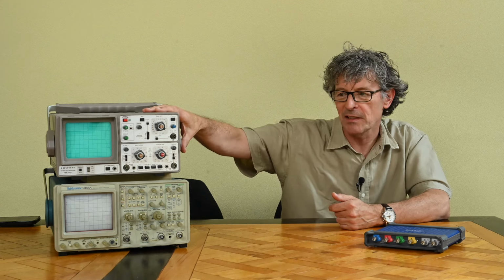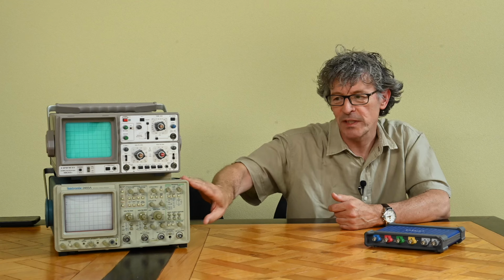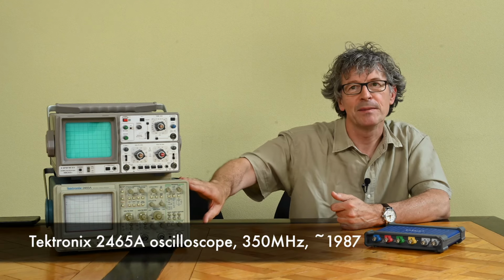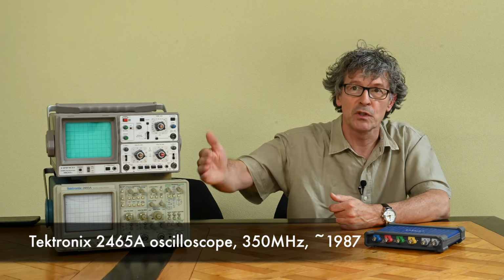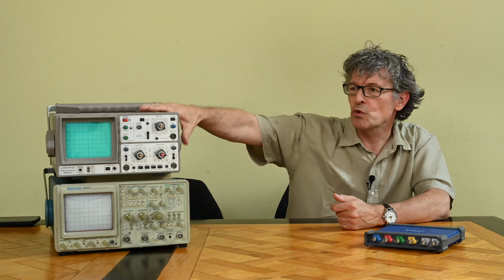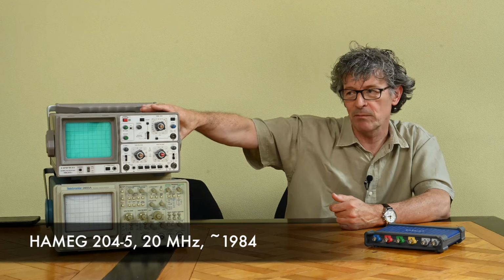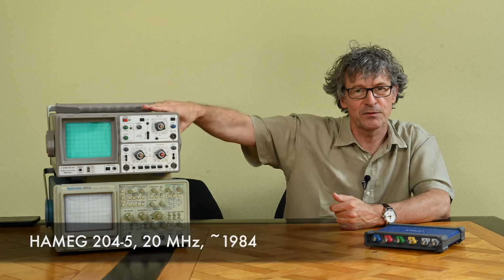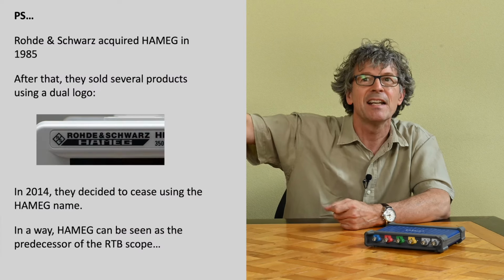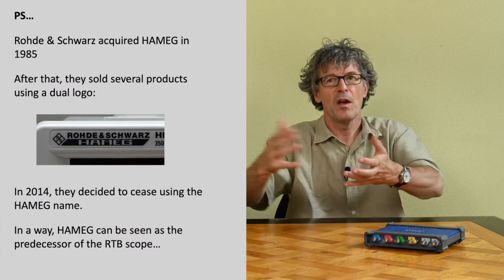Math functions have been with us on oscilloscopes for a fairly long time. I've got two oscilloscopes standing right here, a Tektronix 350 megahertz, I think. It has addition, it has invert, so you can also do subtraction. Also my Hameg scope, I think I bought it when I was about 15 years old, and it still functions perfectly. It's in a very nice state and can do exactly the same thing. So mathematics have already been with us on oscilloscopes for a long time, and for a good reason.